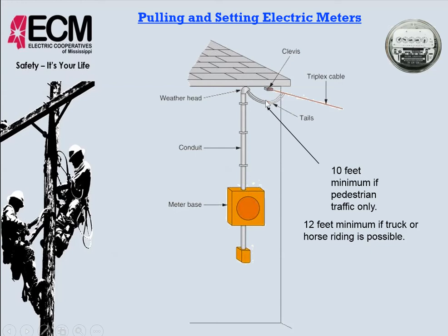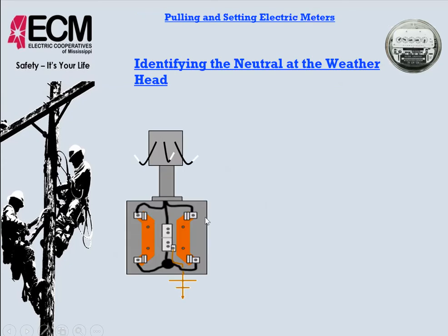So if it was going to be less than 10 feet, your drip loop when it came down, and we need to make sure that we have a drip loop there because we don't want water running inside of our weatherhead. If it's going to be less than 10 feet, this pipe would need to extend through the roof. And then after it extends through the roof, it needs to be sealed. Okay, it needs to have a weatherhead on top. Be sure rain will not get in here, and also the roof needs to have a rain cap on it as well. That seals the roof, so no plywood getting rotten.